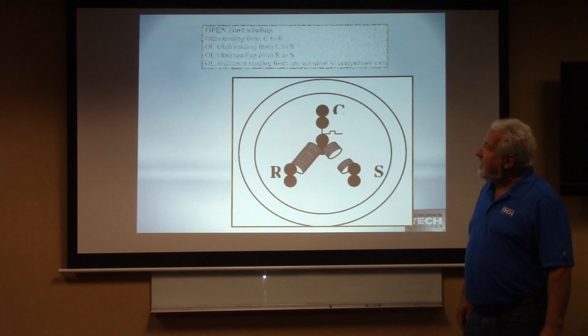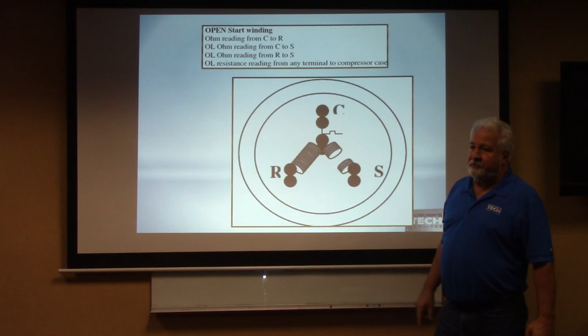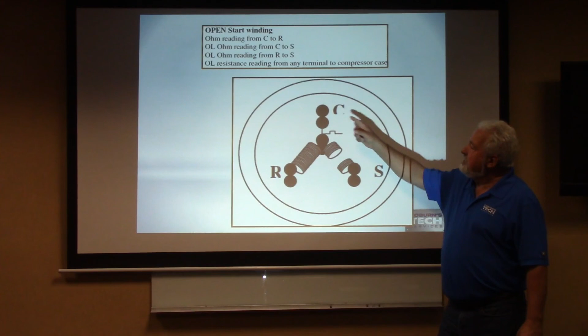In this case, what's wrong with this compressor? Open start winding, we can see it because it's visual. But if I had an open start winding, would I get an ohm reading from common to run? Yes, there's a path. Would I get an OL reading from common to start? Yes, because there's a lot of ohms. Would I get an OL reading from run to start? Yes. Would I get an OL reading from any of those to the case? Possibly, on start.